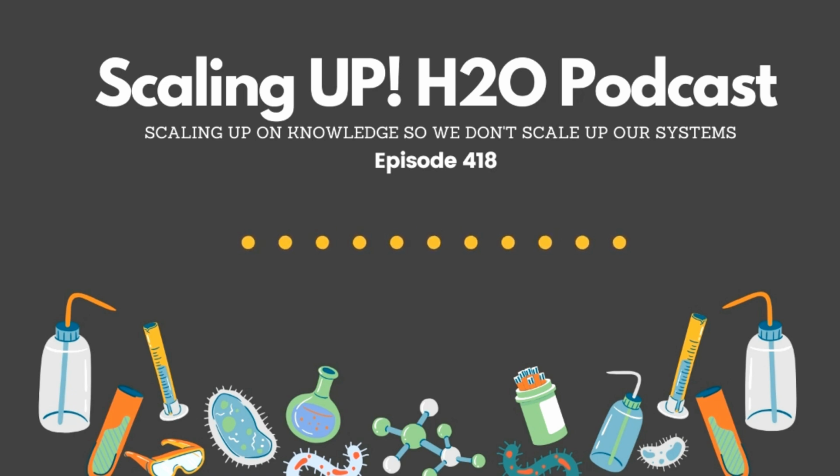So I don't think that this is a material that's used in every single application. I started off kind of answering your question by saying, look, the most effective and the lowest cost, the most broadly used with the most flexibility approach within phosphorus chemistry is using orthophosphate and polyphosphate together. I think that's still the answer for a vast majority of the applications. I do think, though, that the maleic based materials and other phosphonates are great choices situationally.